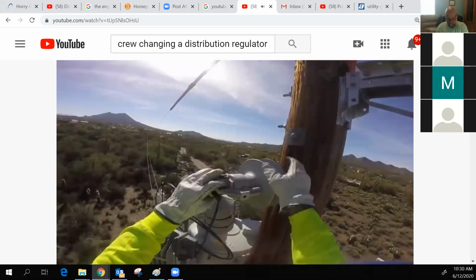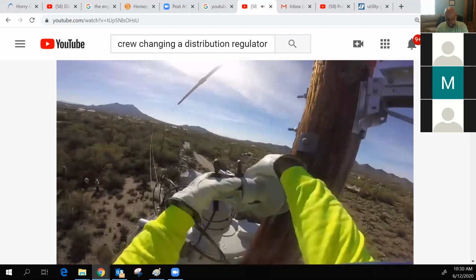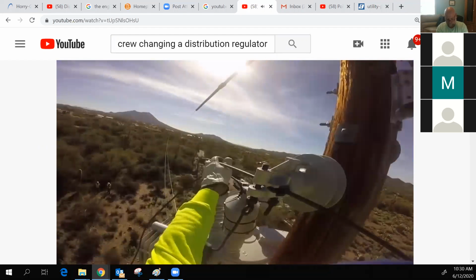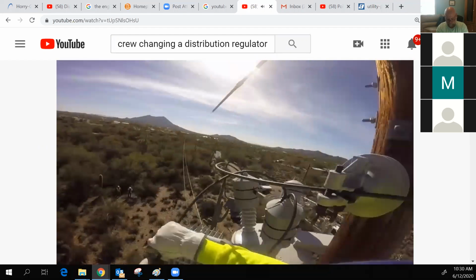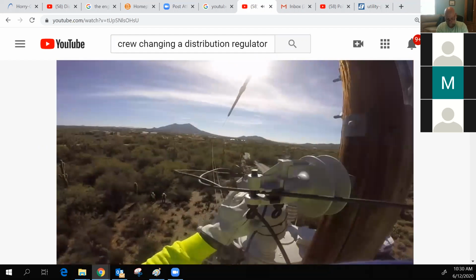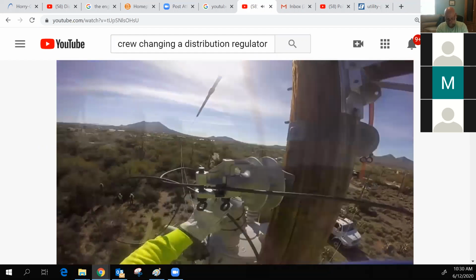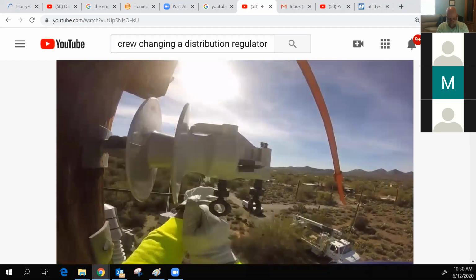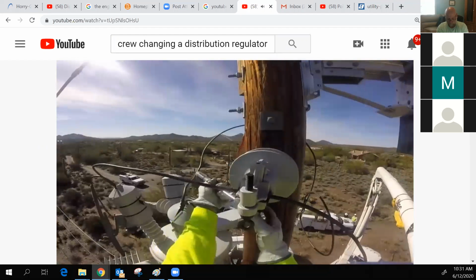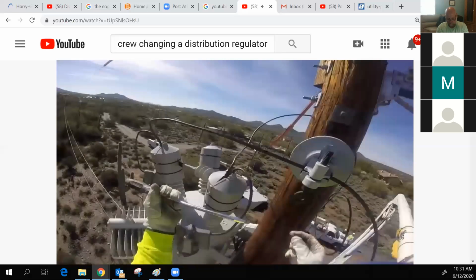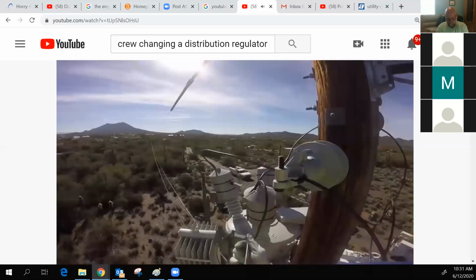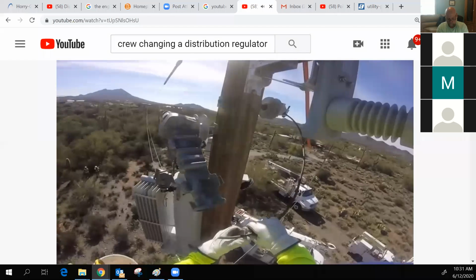Next, they install some clamp top insulators to the pole, and those support the regulator leads. You see him feeding those through the clamp top insulators. Next, he's going to tighten some torque bolts on these clamp top insulators. They have to be tightened to between 75 and 85 pounds of torque, and so what they do is tighten them until the eyes actually break off.